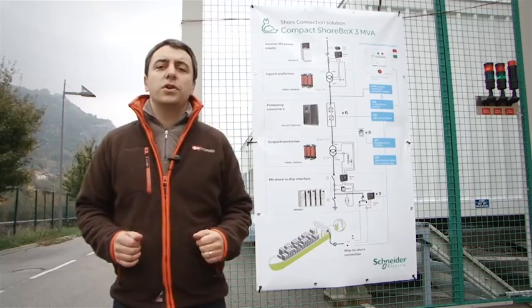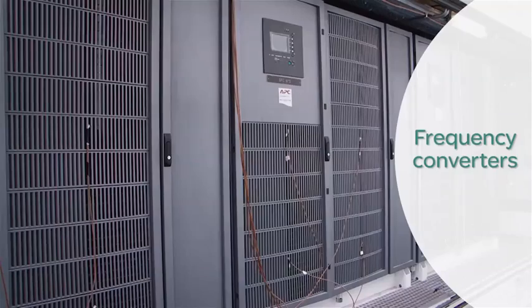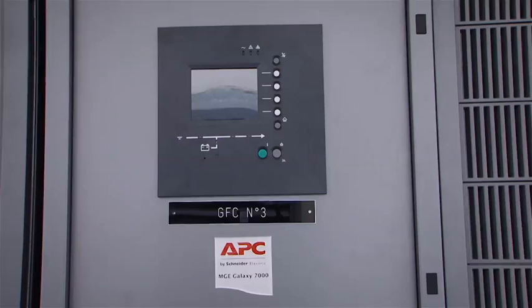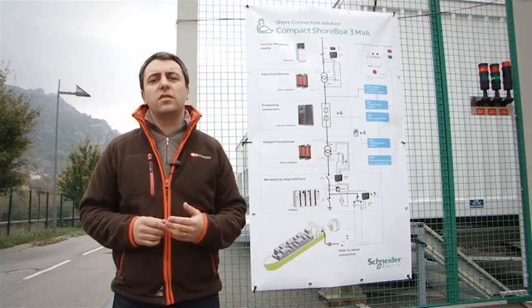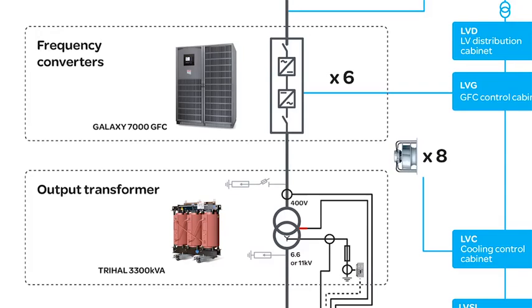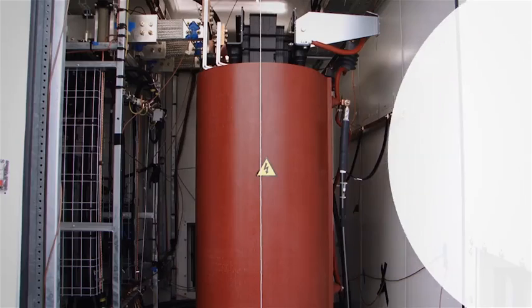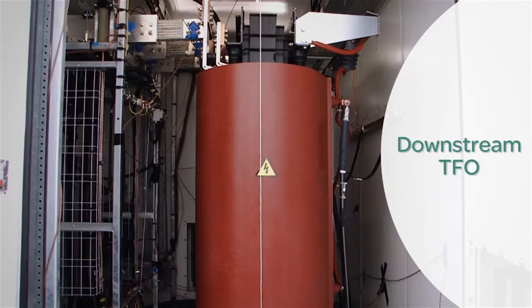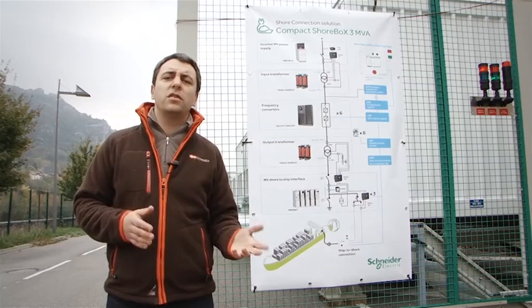The frequency conversion is made by specific components called GFC. Each of them has a rated power of 500 kVA, and its role is to make the conversion from 50 to 60 Hz. We'll find a second transformer, very similar to the first one, whose role is to raise the voltage up to the ship level. It could be 6.6 or 11 kV.